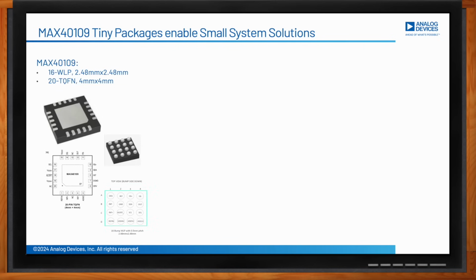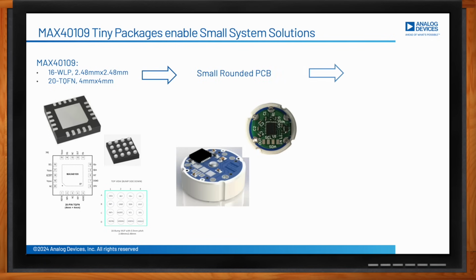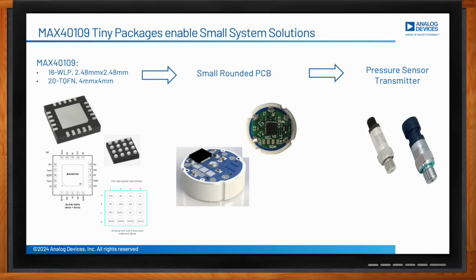Okay, so what else is important in this application, Maurizio? Yes, so space is also very critical in pressure sensor transmitters. Because this system has a long cylindrical shape, the PCB with the sensing element and the analog front end, like the MAX40109, is rounded and small in diameter, anywhere between 10 millimeters to 20 millimeters at the most. Such a PCB requires a small package, all features integrated analog front end. The MAX40109 meets all these requirements by providing a one-chip solution in a tiny space. It comes with two packages, a 16-pin wafer-level package with 2.5 millimeter by 2.5 millimeter size, and a 20-pin TQFN with 4 millimeter by 4 millimeter.